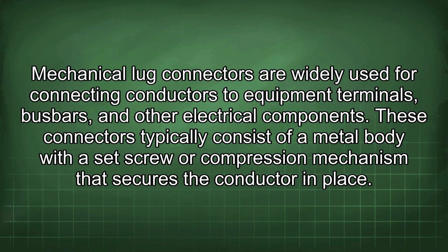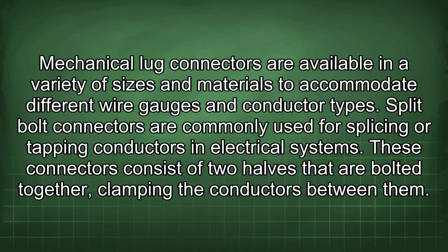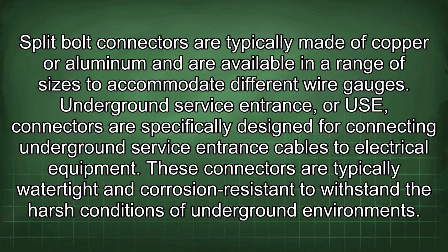Mechanical lug connectors are widely used for connecting conductors to equipment terminals, bus bars, and other electrical components. These connectors typically consist of a metal body with a set screw or compression mechanism that secures the conductor in place. Mechanical lug connectors are available in a variety of sizes and materials to accommodate different wire gauges and conductor types. Split bolt connectors are commonly used for splicing or tapping conductors in electrical systems. These connectors consist of two halves that are bolted together, clamping the conductors between them. Split bolt connectors are typically made of copper or aluminum and are available in a range of sizes to accommodate different wire gauges.